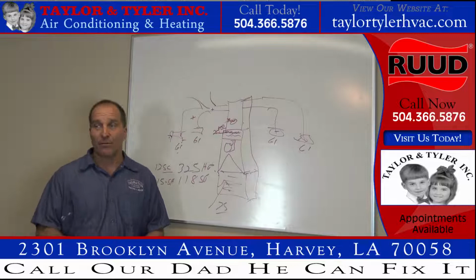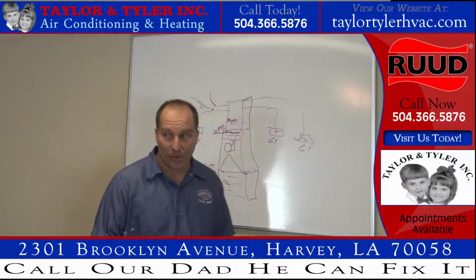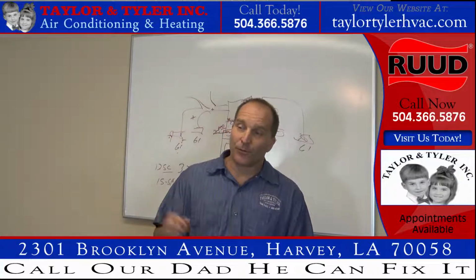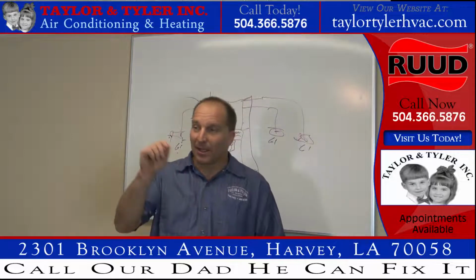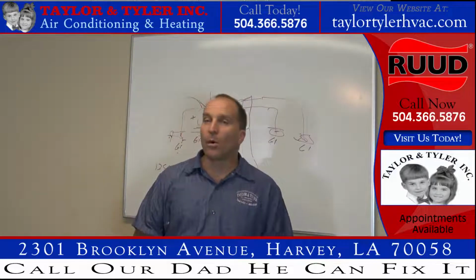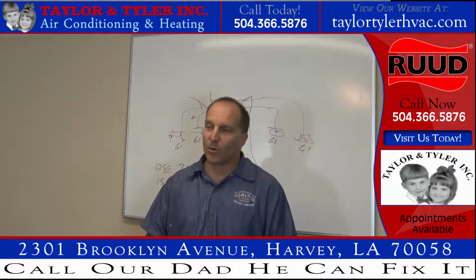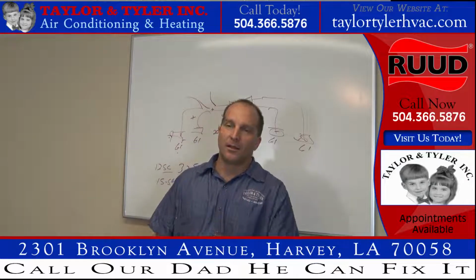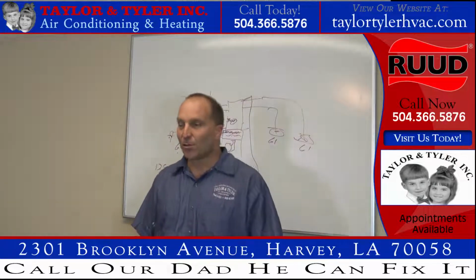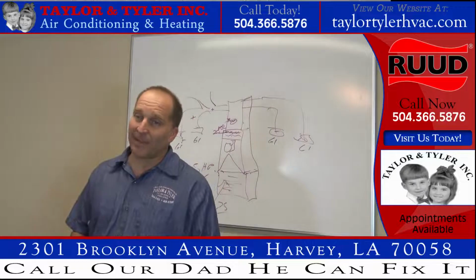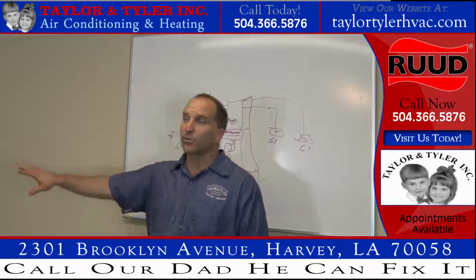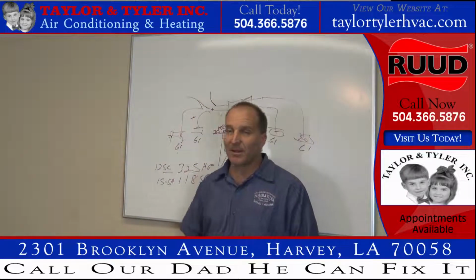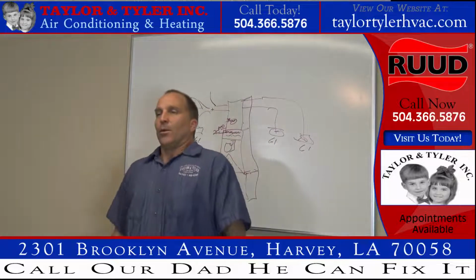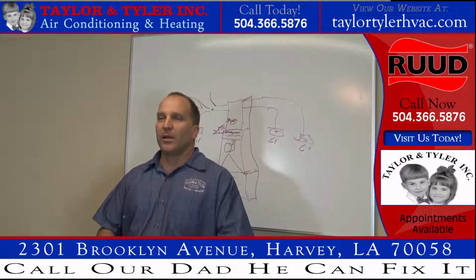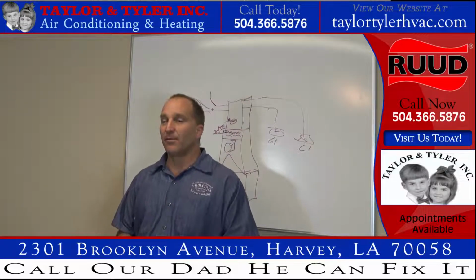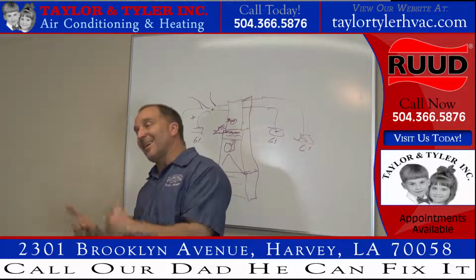So I actually have a form that I want you to carry in your truck with you. If you fill out all the paperwork on this form, every number on it, you will answer your own questions 95% of the time. Just like if you call a technician for technical support at Lennox or Rheem or whatever may be the case, he's going to ask, what's your head pressure, suction pressure, superheat, subcooling, and delta T? Matter of fact, they're recorded before you even get them.